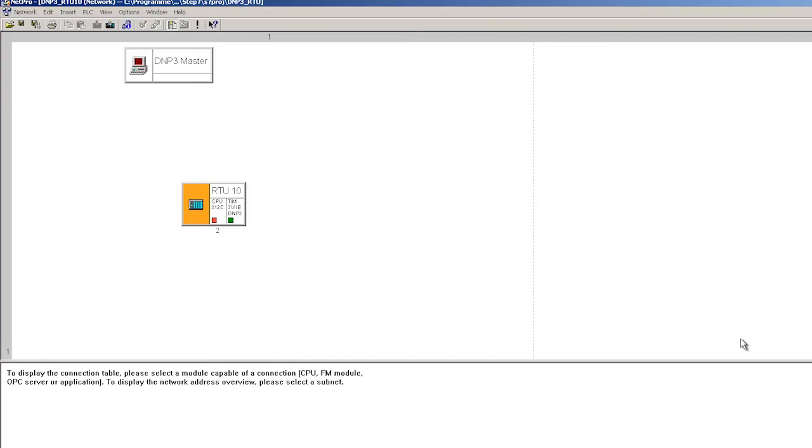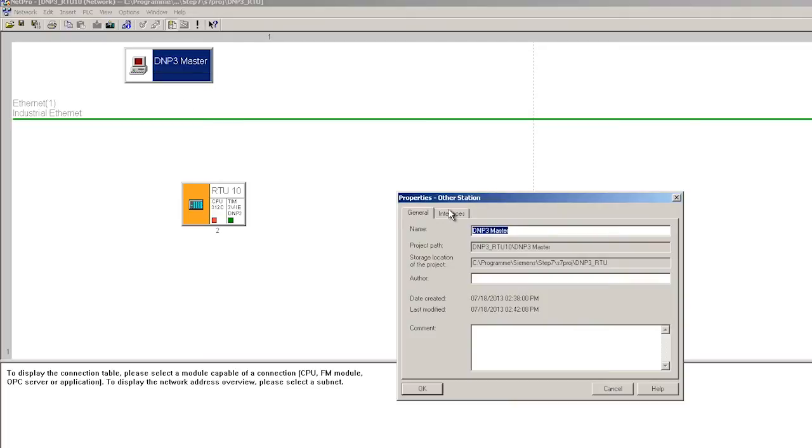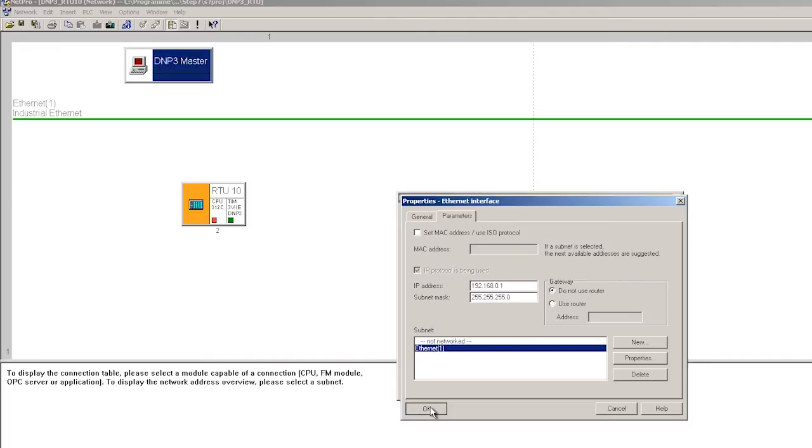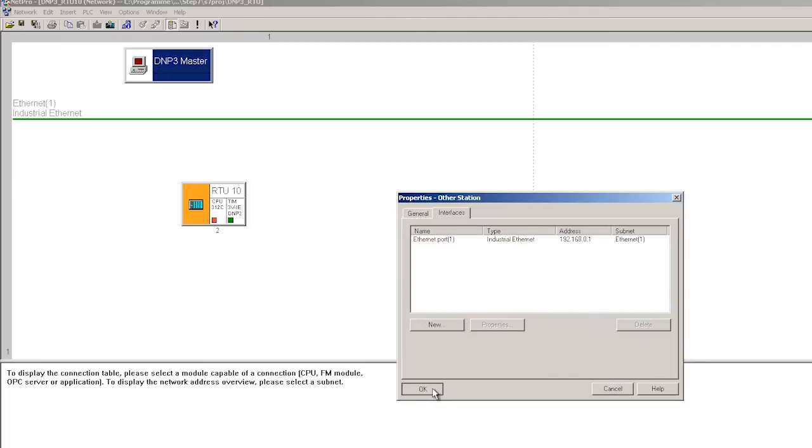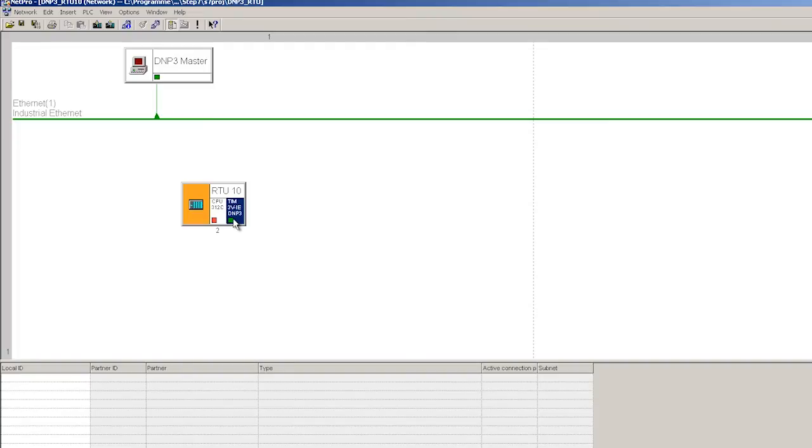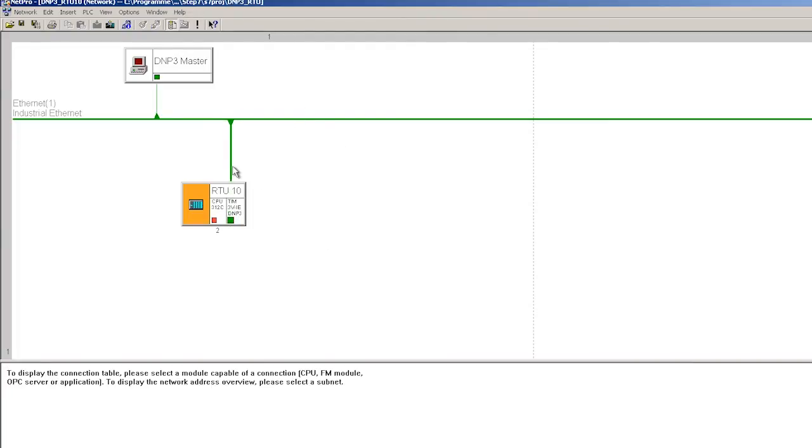In NetPro, I configure an industrial Ethernet and provide the control center with an industrial Ethernet connection. I assign the IP address according to the task and connect the control center with the Ethernet. The TIM module is also connected with the Ethernet network and the IP address modified according to the task.